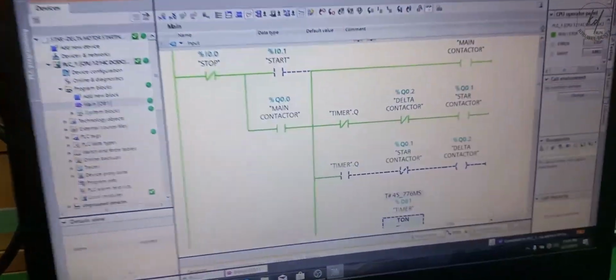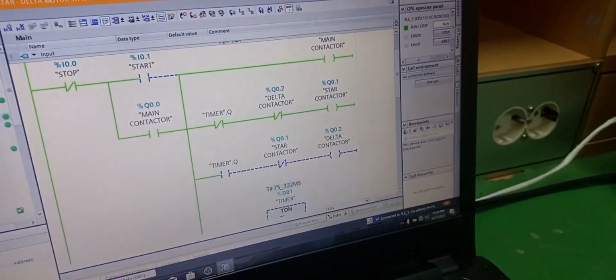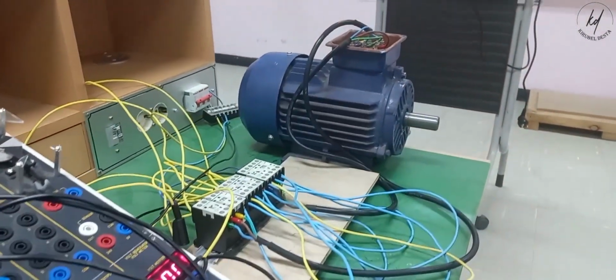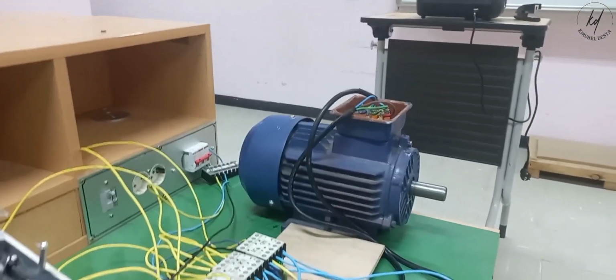This starter employs the star-delta method for starting the motor, which involves changing the motor's winding connection from a star configuration to a delta configuration once the motor reaches a certain speed.